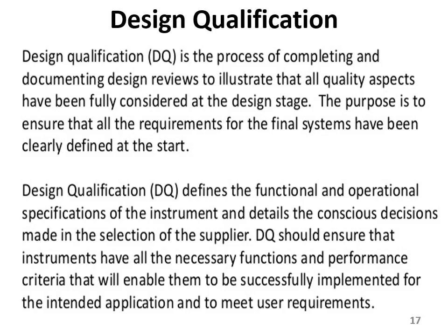So DQ, or design qualification, is actually the functional and operational specifications of the instrument, and details regarding the conscious decisions made in the selection of the supplier. DQ should ensure that the instrument has all the necessary functions and criteria that will enable you and the machine to successfully go through the system and implement all the requirements and the needs of the user.